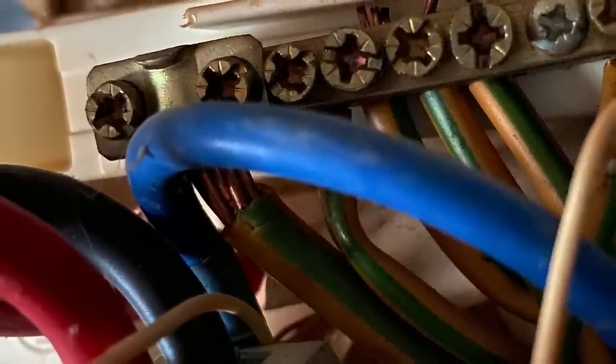We're not going to just write it down and report it back for the sake of undoing a screw property. It's probably more work, considering I would remove that conductor to undertake my external earth fault loop impedance anyway. It's probably more work to write it up on the certificate and code it accordingly and then quote for it than it is to just sort it while you're there.